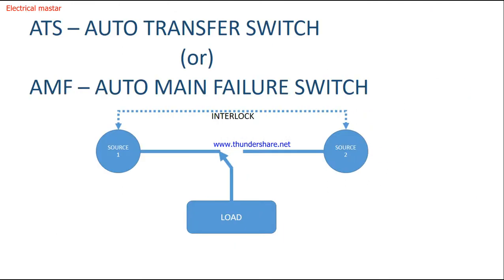ATS means Auto Transfer Switch, and it is also called Auto Main Failure switch. This ATS is used to control two sources — whenever source 1 fails, it will connect the load to source 2. Similarly, when source 1 comes back, it returns the load from source 2 back to source 1. That is the ATS panel.